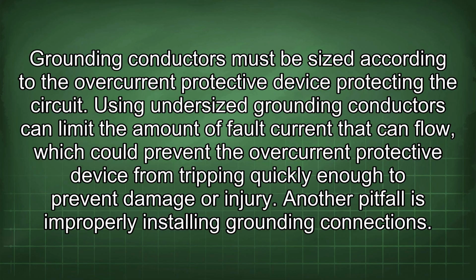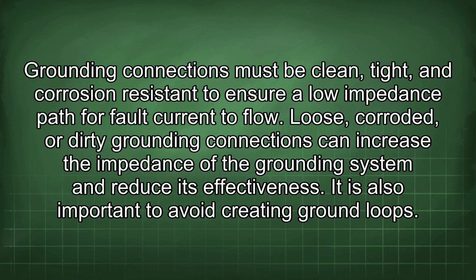Another pitfall is improperly installing grounding connections. Grounding connections must be clean, tight, and corrosion resistant to ensure a low impedance path for fault current to flow. Loose, corroded, or dirty grounding connections can increase the impedance of the grounding system and reduce its effectiveness.